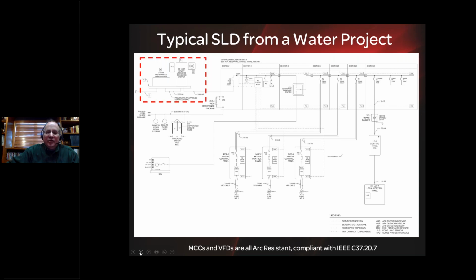So here we can see in the upper left-hand corner, that is the utility service entrance equipment. The utility in this case did allow for high resistance grounding. Okay? So even though it was a YY transformer, they broke the bond between HO and XO and the bond between XO and ground. And since they floated the Y, it's essentially the equivalent of a delta other than the phase shift. So that would allow for high resistance grounding.